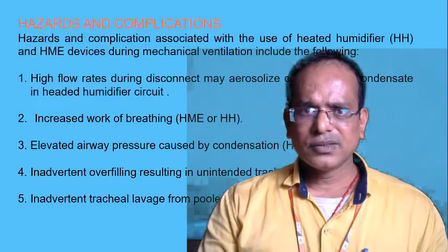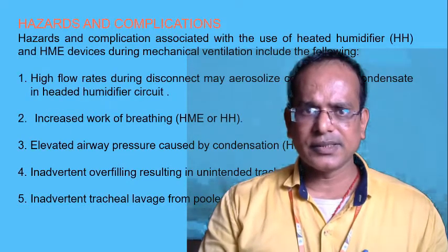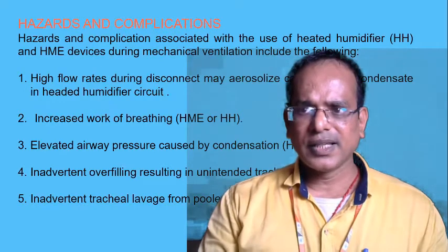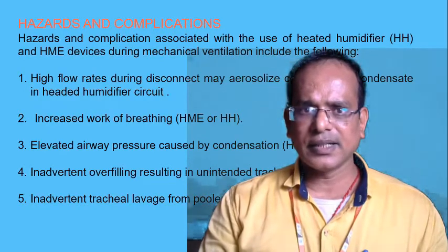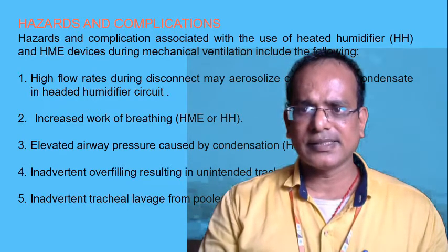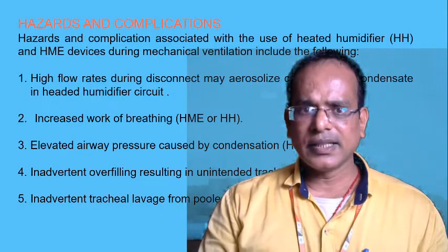Hazards and complications. Hazards and complications associated with the use of heated humidifier (HH) and HME devices during mechanical ventilation include the following. High flow rates during disconnection may aerosolize contaminated condensate in the heated humidifier circuit.